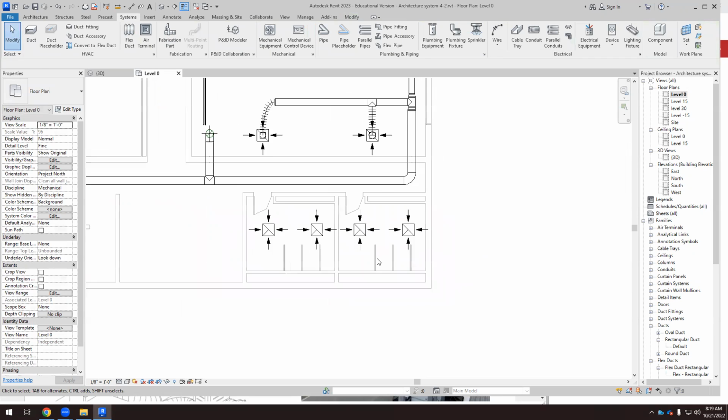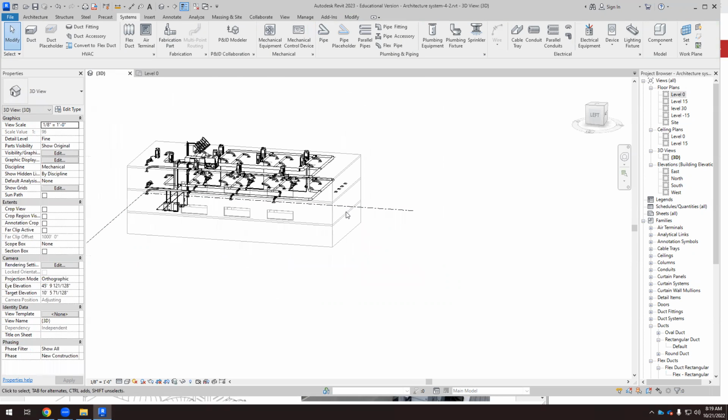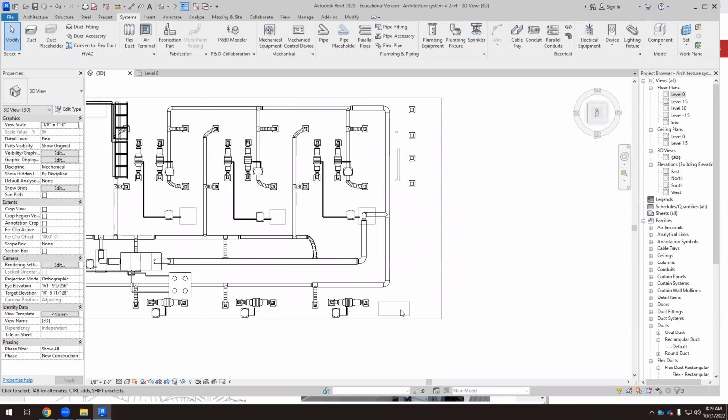And now we only have to connect another duct, and that duct has to go all the way through this shaft. So we have to connect this horizontally, and at this point, we have to get rid of it. We don't have to connect this to the air handling unit, and we don't need a supply and return. The exhaust is just exhaust. We have the exhaust grills, and then we need to connect the horizontal to the vertical pipe, and then extend that vertical pipe beyond the roof level.